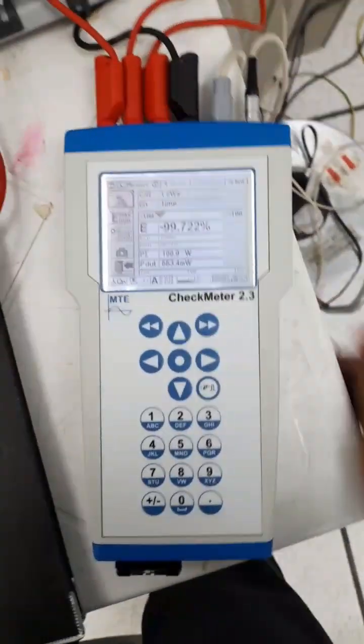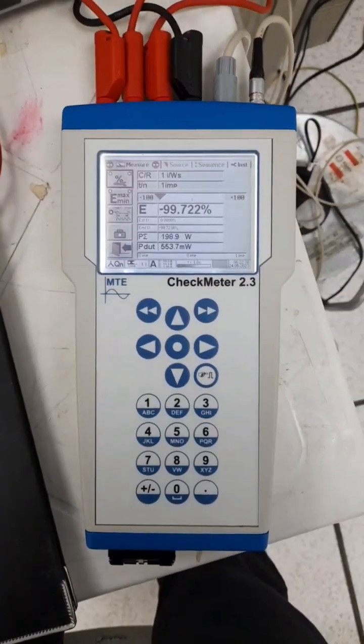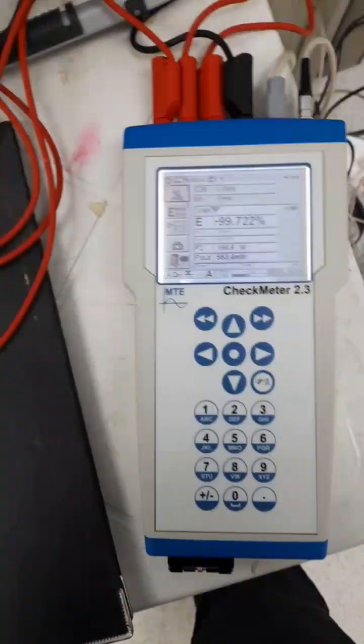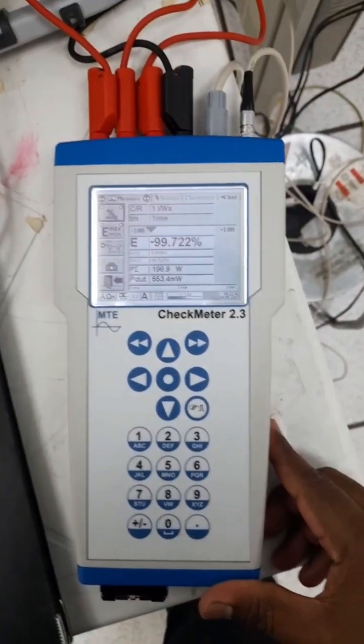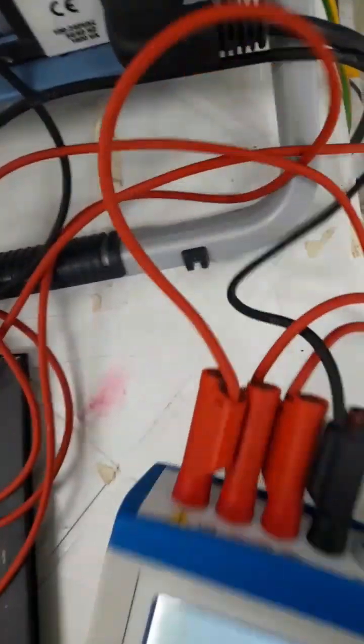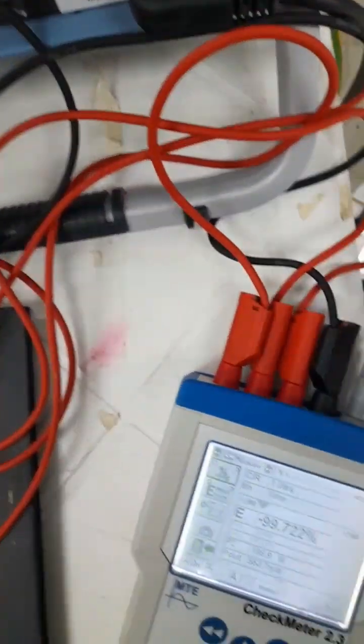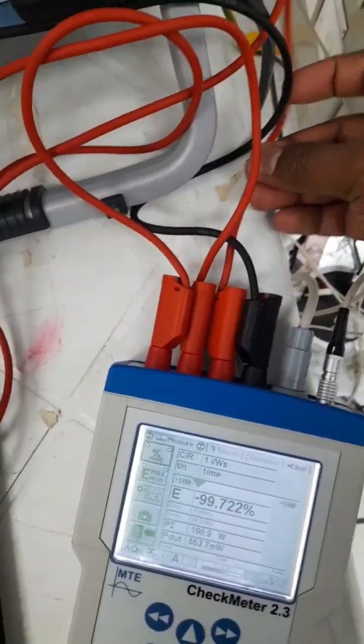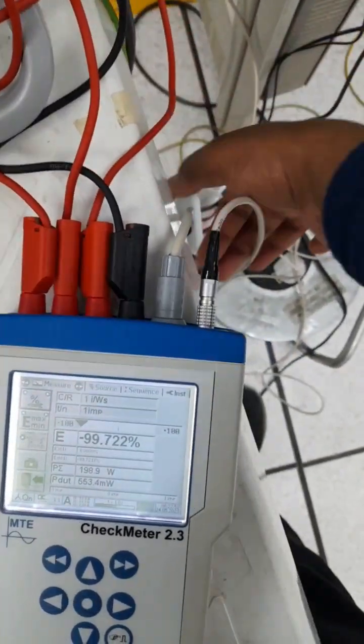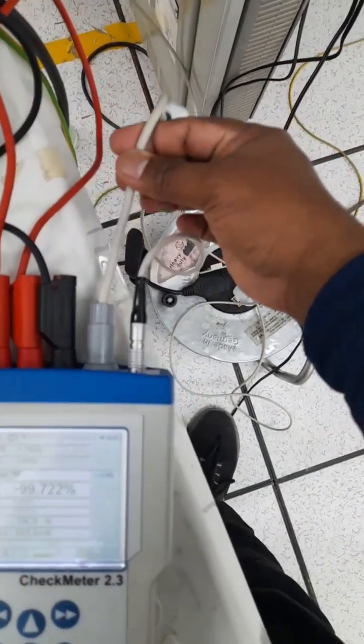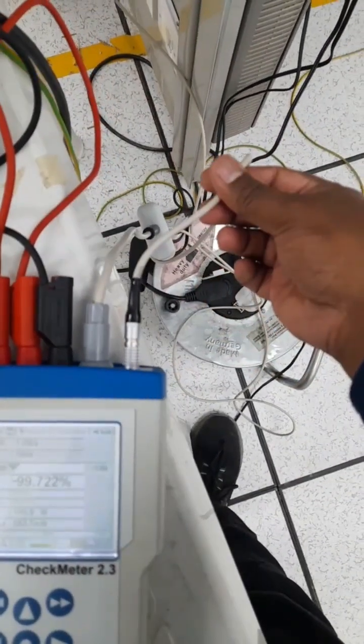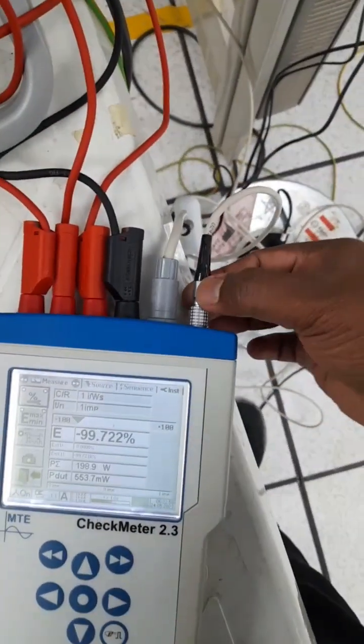Okay, now I'm going to do the accuracy test for the energy meter by using this CheckMeter 2.3. Initially, the connection was these all voltage cables going to neutral and this is the current, and this is for the scanning head sensor. I'll show you the connection.